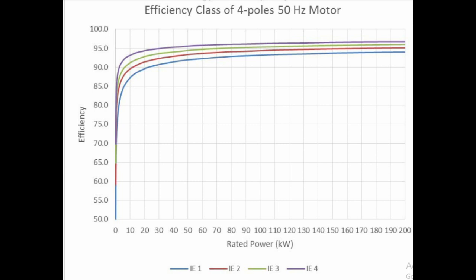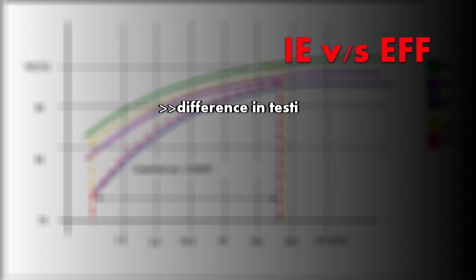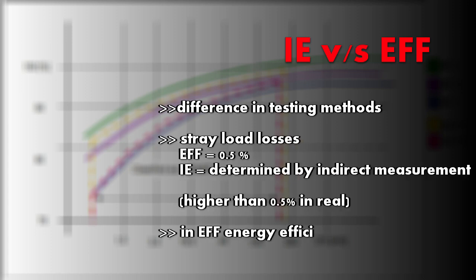The IE classification applies to three-phase continuous duty electric motors with two, four, six, or eight poles. The output range should be between 0.12 kilowatt and 2000 kilowatt, rated output voltage up to 1 kV, frequency between 50 to 60 Hz, ambient temperature between minus 20°C to plus 60°C, and altitude up to 4000 meters above sea level.